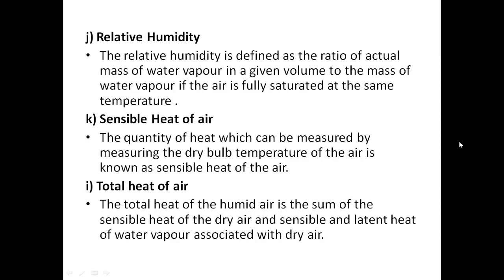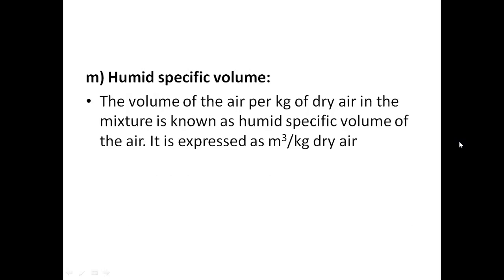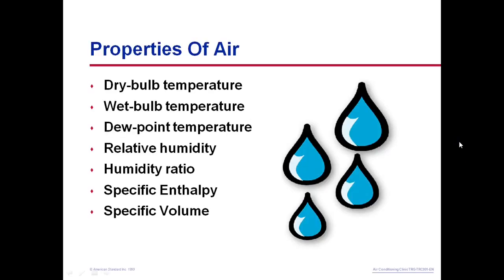Sensible heat of air is the quantity of heat measurable by measuring the DBT of air. Total heat of air is the sum of sensible heat of dry air and both sensible and latent heat of water vapors. Humid specific volume is the volume of air per kg of dry air in the mixture, expressed as cubic meters per kg of dry air — it is the inverse of density.